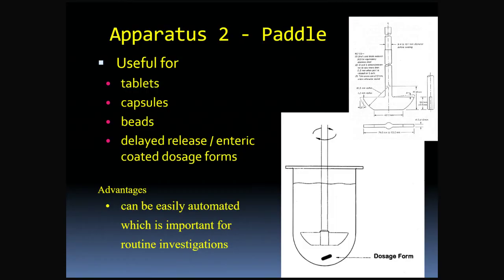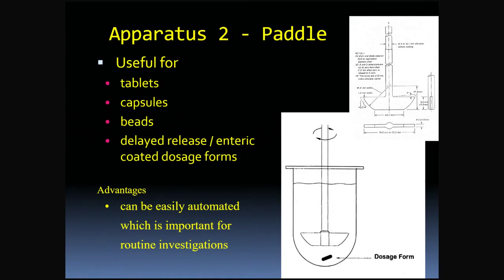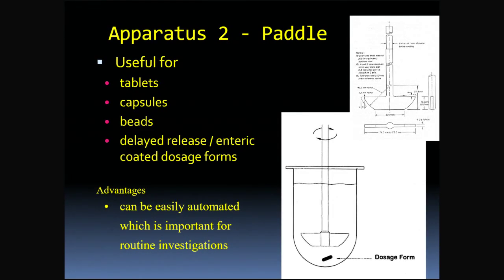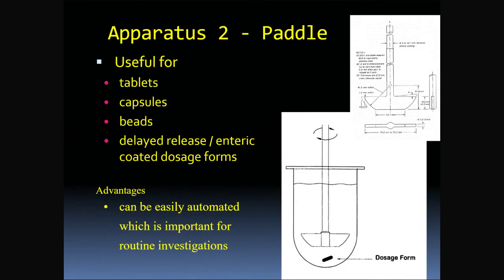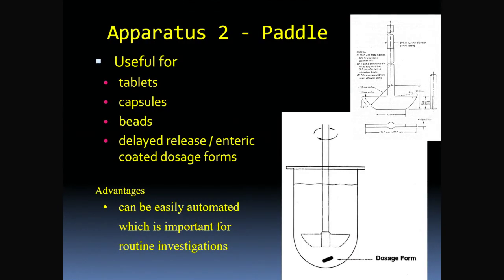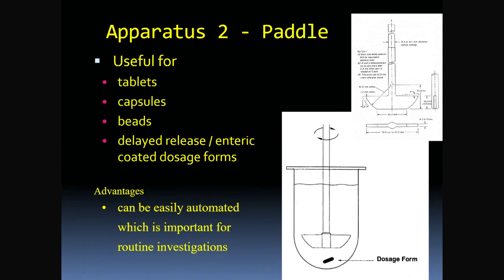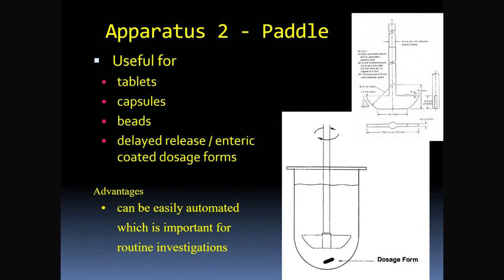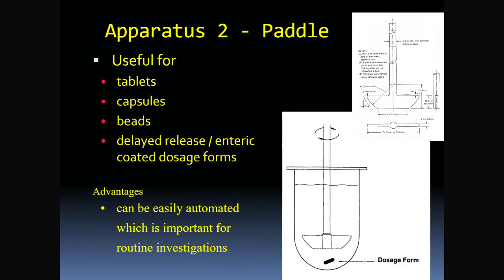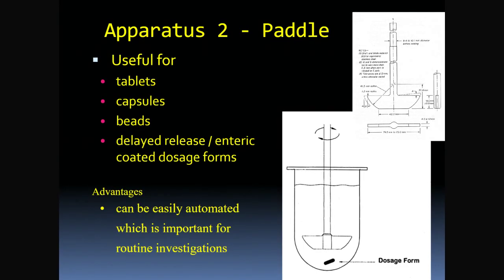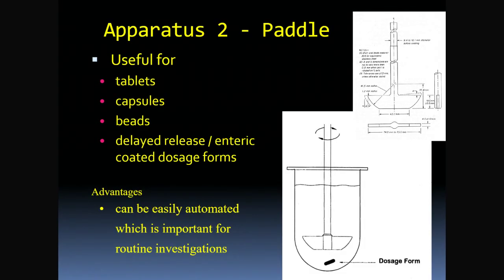The paddle width and height are strictly standardized to ensure that the fluid velocity profiles generated are reproducible across different laboratory settings. The mechanical simplicity of this design allows for seamless integration into automated sampling systems, which maintains the integrity of the concentration gradient during the long-duration tests required for delayed release formulations.